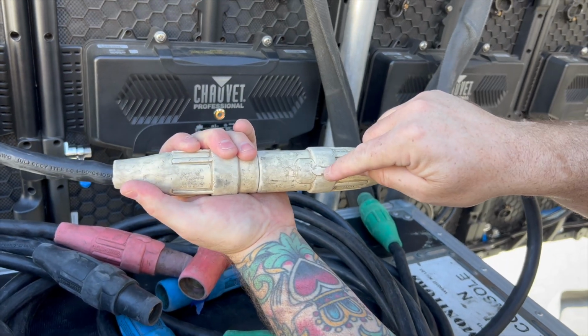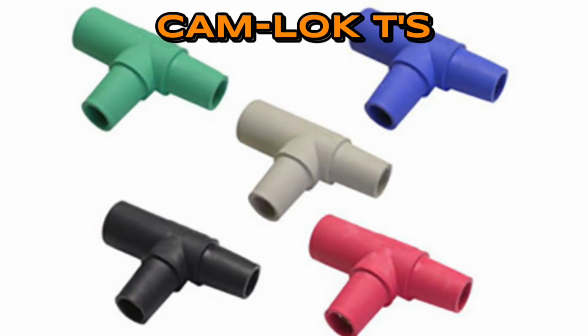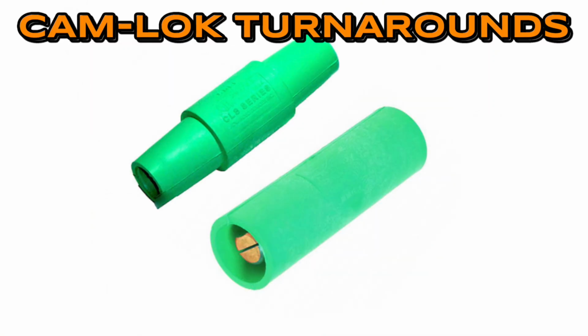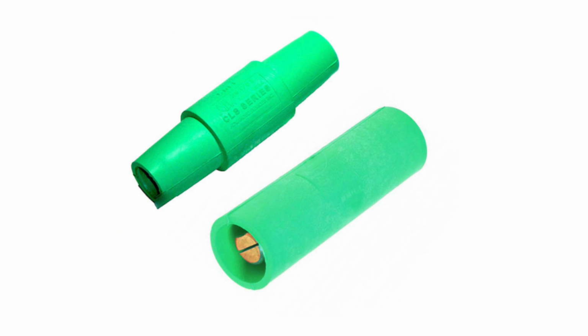In a typical touring kit, you will also have Cam-lok T's if you need to split the power into a couple different directions. You will also be carrying a pair of Cam-lok turnarounds, male to male and also female to female. Ground and neutral may be reversed, one or both, but the hot phases will always be the same direction. They should never be reversed. Female at the service, male at your distro.